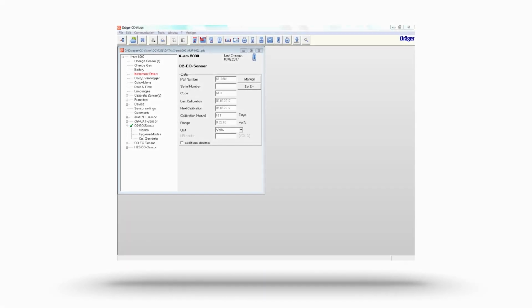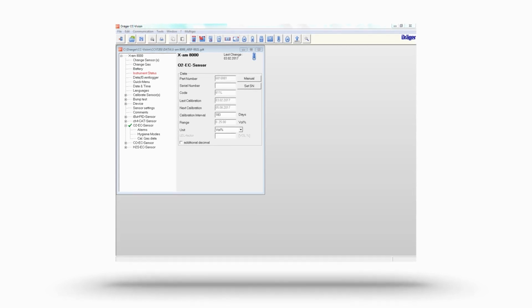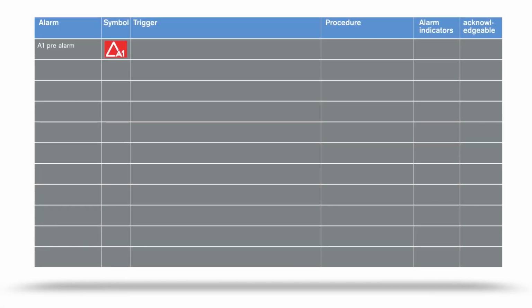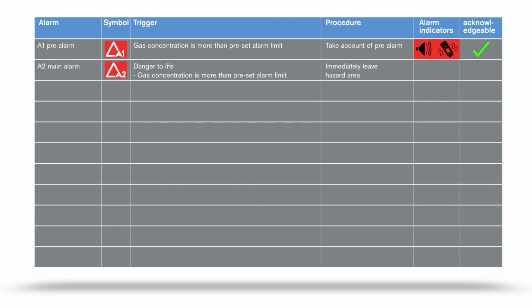Generally speaking, you can change alarm thresholds and parameters using the Dräger CC Vision PC software. The A1 pre-alarm sounds when the concentration is higher than the set threshold value. There is not yet acute danger. This alarm can be acknowledged by pressing the green OK button. An A2 main alarm indicates danger to life. If this alarm sounds, leave the hazard area immediately. This alarm is non-acknowledgeable. The alarm display can be optionally supplemented by a hazard symbol.